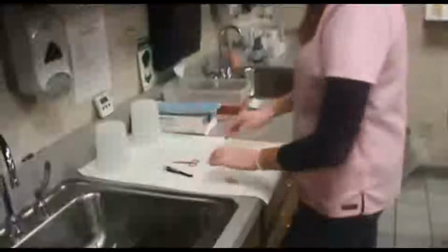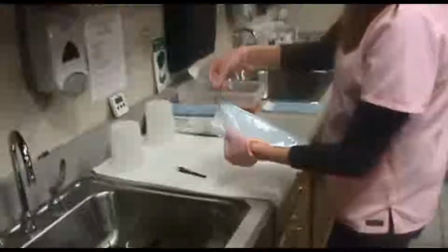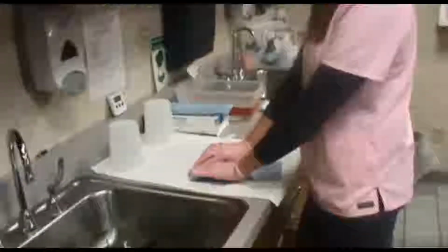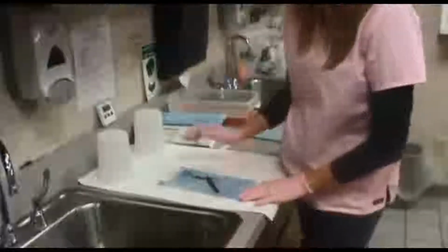Put on new gloves, dry the excess water, and package your instruments in the open position. Tear off the plastic seal and fold at the perforated line. This is an incorrect fold because there is not an airtight seal. We have found a few instruments with material still stuck to them.